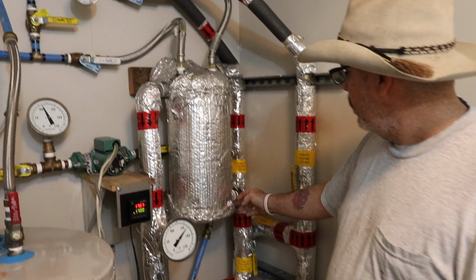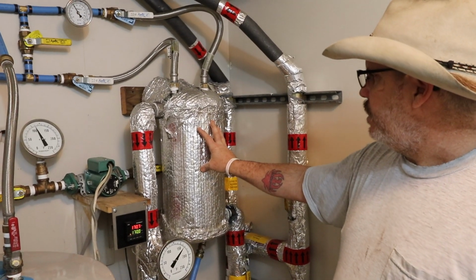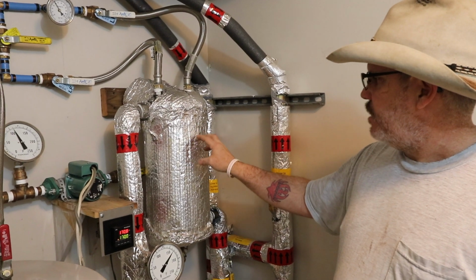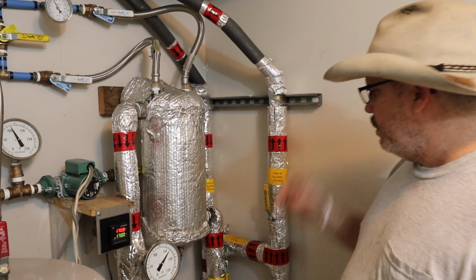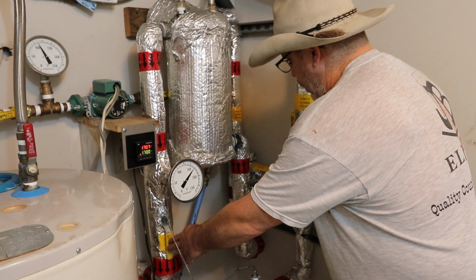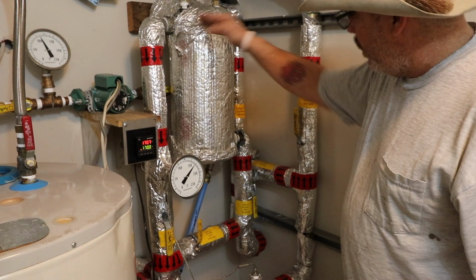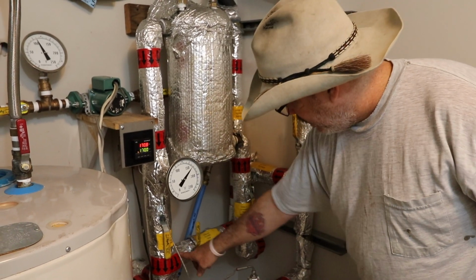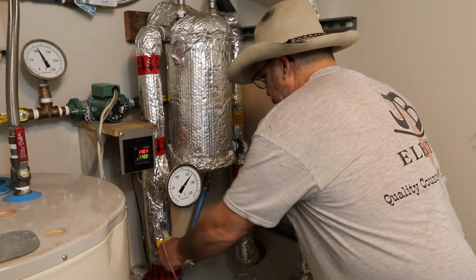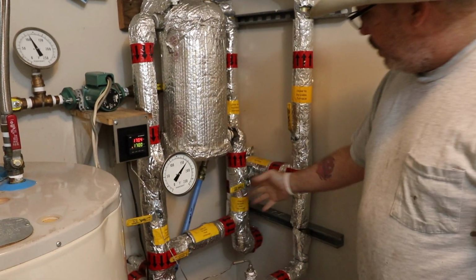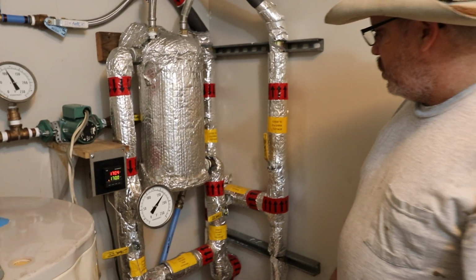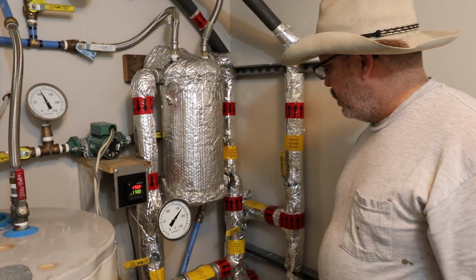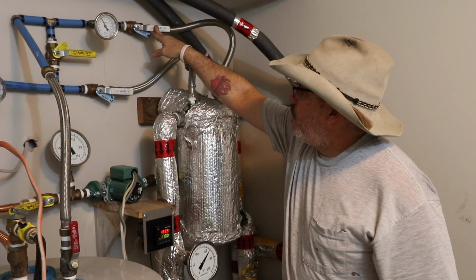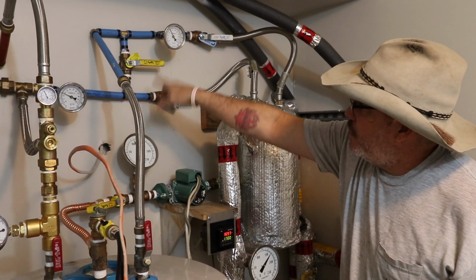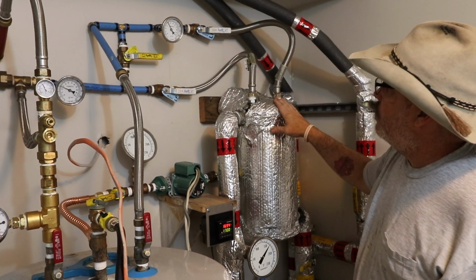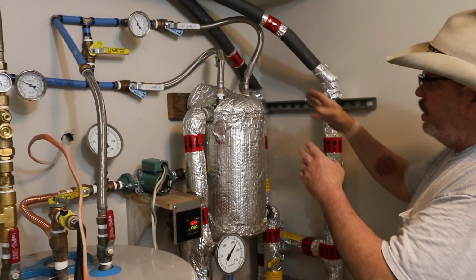I've got unions here so that if I need to deal with any scaling or anything that binds up in here, collects or whatnot, or I need to flush it out, I just valve this system out, and instead of my return coming through here and then out, my return will just come this way and then out, and I just valve it out there. Right now I just bypass this whole heat exchanger, and I can undo these unions, drain the system. I can bypass my cold water here, so my cold water will go straight into my water heater without going through this, if I ever had to take this out, repair it, or got a leak on these hoses or whatever.